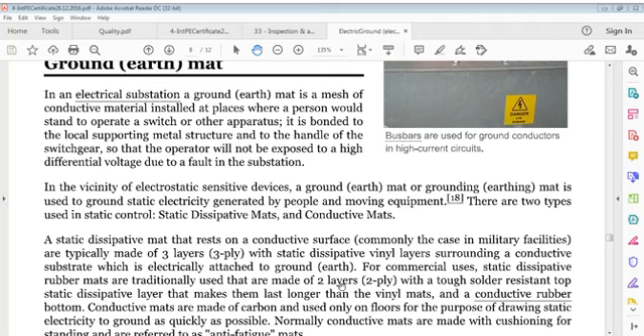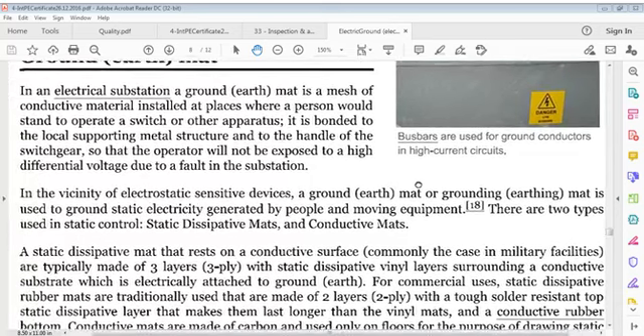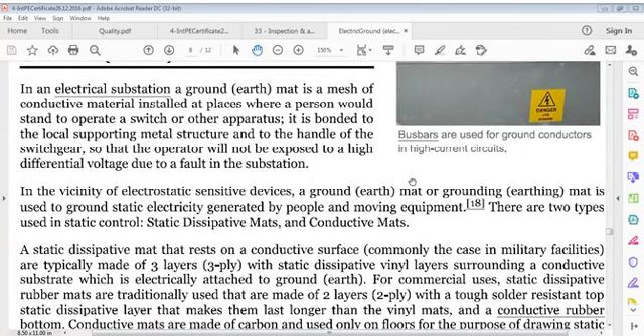I'm saying that in an electrical substation, we are talking of an electrical substation, a ground mat is a mesh of conductive material installed at places where a person would stand to operate a switch or other apparatus. It's bonded to local supporting metal structures and to the handle of the switchgear so that the operator shall not be exposed to a high differential voltage due to a fault in the substation.